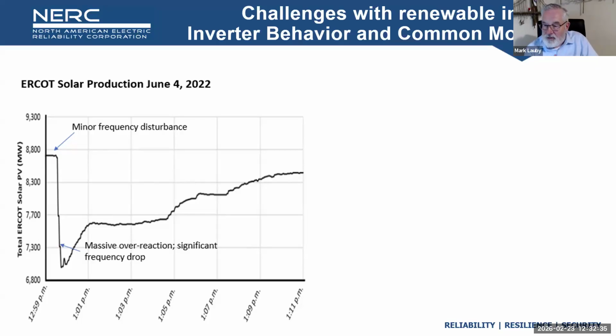But what we see here in this particular case in Texas is a similar type of problem, where they almost got to their maximum single contingency, which would be very serious. There's a certain level you simply don't want to reach. You're getting close to your under-voltage and under-frequency load shedding, just a massive overreaction to a simple line-to-ground fault. They're working on this. They fixed some of it because we wrote standards, and some were able to take the grandfathering off and ask them to work with their existing controllers and improve them.